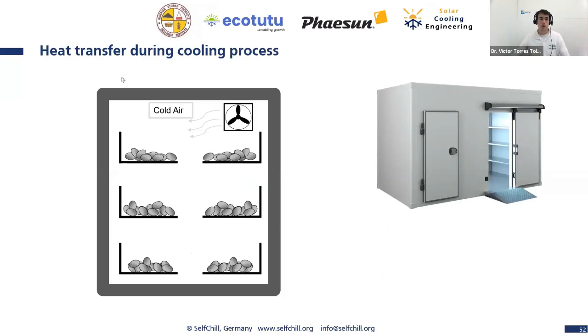What else? Once we know the cooling speed, so we know how fast our produce will cool down, then we can calculate, depending on the amount of products that we have, how much energy we need to cool down this agricultural produce, right? So we call it here heat extracted from the product. So we have here the cold room, the products inside, the cold air, and depending on how much product we have, we will have more or less heat extracted from the product. Depending on how fast the cooling curve is, how fast the product cools down, this energy will take place in a shorter or a longer time, which is also important. We need to know if this energy is distributed all over the day, or it is only happening at night, or whenever we enter the products inside the cold room.